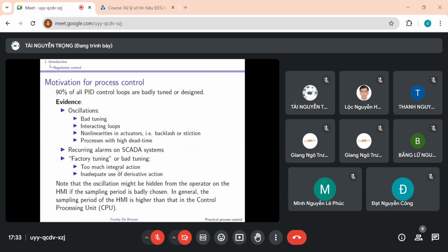As you can see, 30% of the loops have control valves in poor condition, 60% have poor loop tuning, 85% have poor loop design, so problems with the control structure, 15% of the controls are in manual mode, and 30% of the loops are not performing according to the control objective. With what we have seen before, we can certainly agree that an abnormally high quantity of control loops are badly tuned or badly designed. This means that the control structure is not adequate.